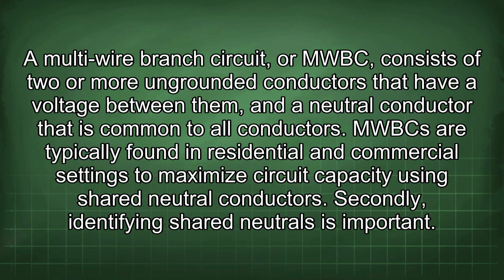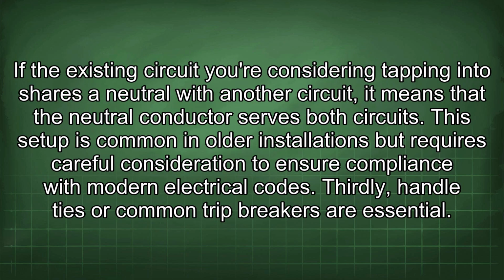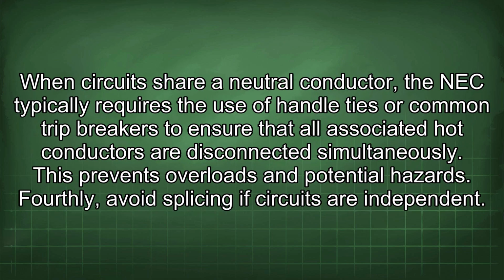Secondly, identifying shared neutrals is important. If the existing circuit you're considering tapping into shares a neutral with another circuit, it means that the neutral conductor serves both circuits. This setup is common in older installations but requires careful consideration to ensure compliance with modern electrical codes. Thirdly, handle ties or common trip breakers are essential. When circuits share a neutral conductor, the NEC typically requires the use of handle ties or common trip breakers to ensure that all associated hot conductors are disconnected simultaneously. This prevents overloads and potential hazards.